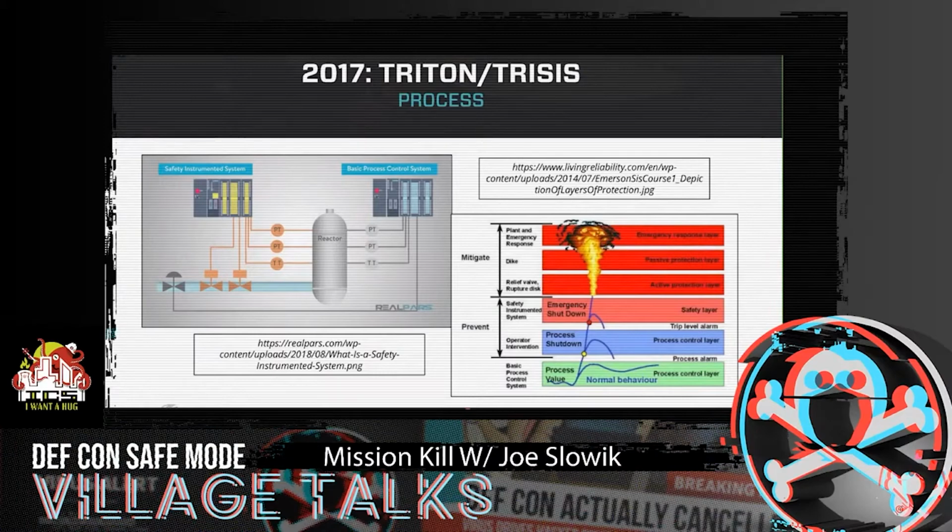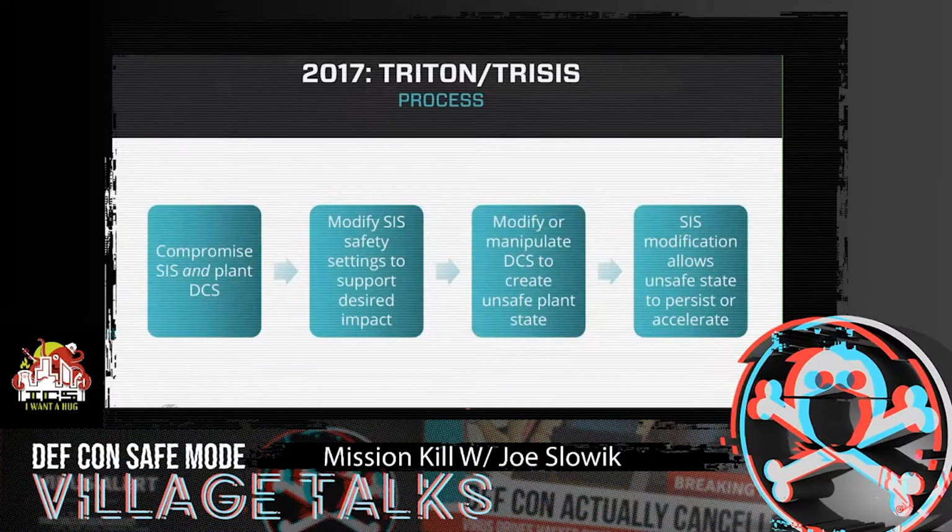So just because you remove the safety layer doesn't mean that you're setting up a plant for absolute tremendous levels of destruction, it still makes for a very hazardous environment where potentially nasty things can take place. If we start looking at TRITON TRISIS, it becomes important to note that the intrusion itself wasn't just focused on the safety layer, but in talking with the incident responders who worked on the event, the compromise took place through both the safety layer as well as within the plant distributed control system environment.